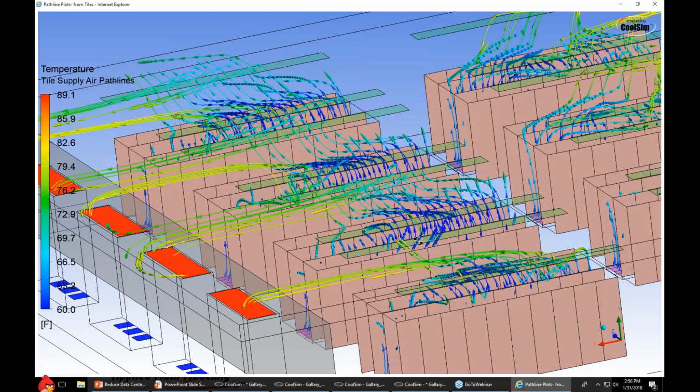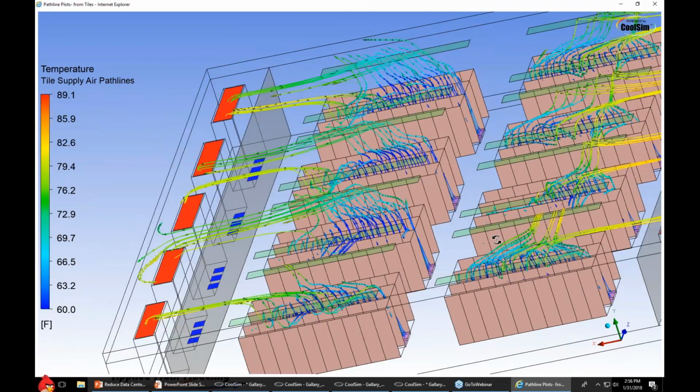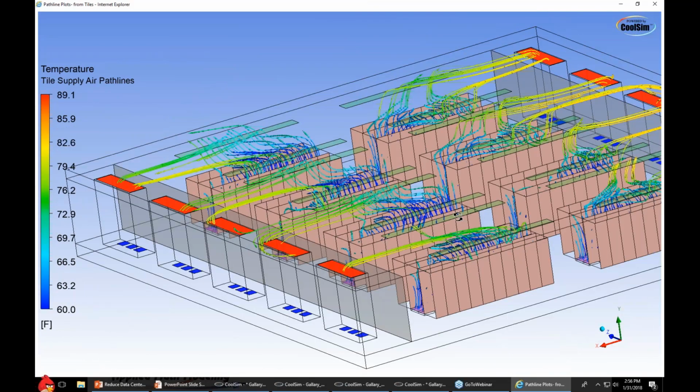What are common thermostat locations seen in the field that are not optimal? I see a lot of junk in the field, a lot of mistakes. It's quite common to see thermostats stuck in the returns of the CRAC units themselves. That's a terrible place for a thermostat. Let me be specific. There are a couple of different thermostats typically used to control these things. One of them is used to control the VFD, and that's either a pressure sensor or a temperature sensor. You can do either one in CoolSim and either one in the field.